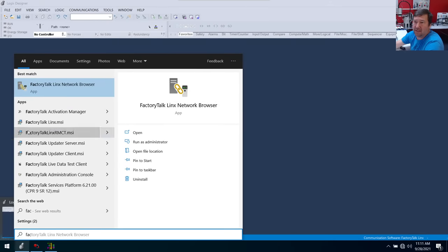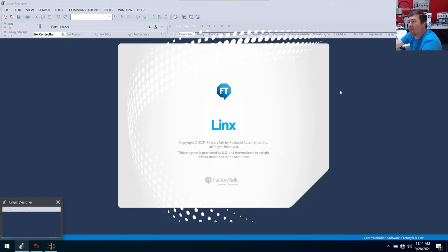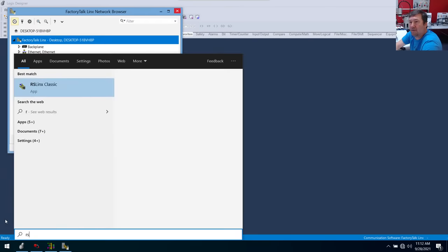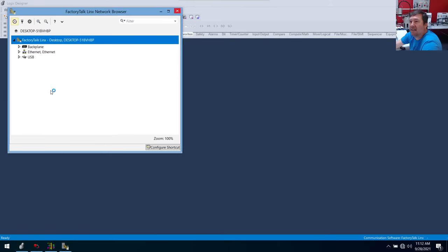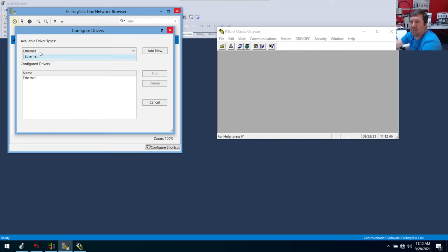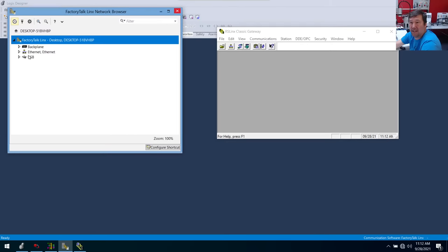None of these three softwares are actually what you communicate with a PLC with. There are actually two communication softwares. We have FactoryTalk Linx — just start typing Factory Talk and you'll get FactoryTalk Linx Network Browser. This is a newer software that Rockwell has come out with, and it will allow you to really connect to most modern PLCs with almost no effort. I'm going to open up the second one — that's RSLinx Classic. This is what a lot of people are more familiar with. The difference is that while they've made Factory Talk super simple, they haven't included the older drivers. If I go to configure drivers on this one, available driver types, you only see Ethernet.